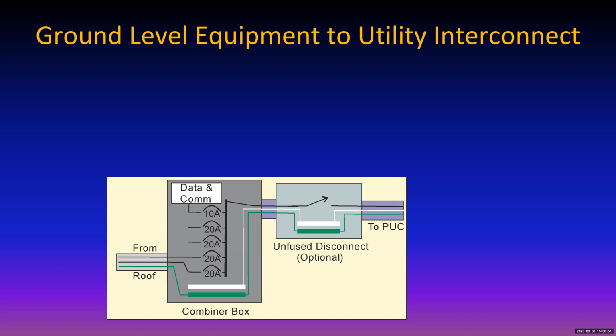And they combine the output, goes to a disconnect that sometimes is optional. Notice you got a neutral bar, and that neutral bar is there as a reference for the data and communication. These are all 2-pole breakers here for 240 volts. The unfused disconnect is optional if the utility requires it. If you're in level 2 of between 10,000 and 100,000 watt AC system, as far as utility call. And then we connect it to the utility.